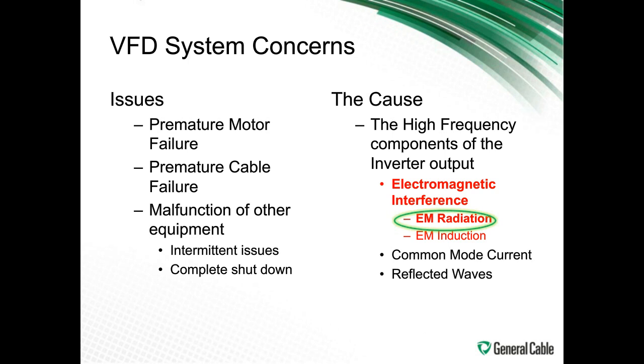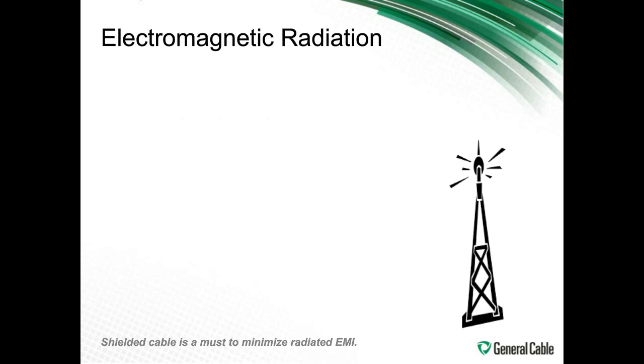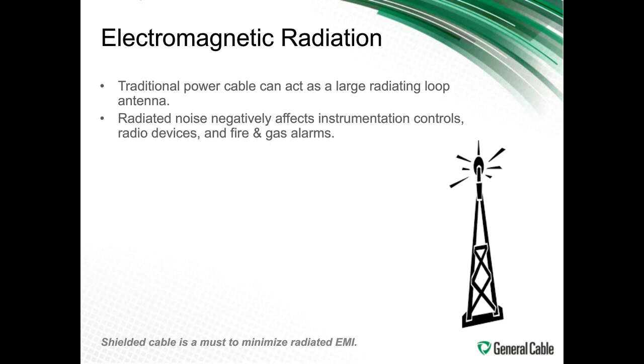So let's talk about electromagnetic interference. That consists of electromagnetic radiation and electromagnetic induction. So these two we will talk about in a little more clarity. Electromagnetic radiation is basically creating a radiated loop antenna that can be created from your system if it's not well grounded. So you get the radiated noise that negatively affects the instrumentation controls, the radio devices, and all the alarms, and the severity is really related to the distance you have from the cable and the equipment.